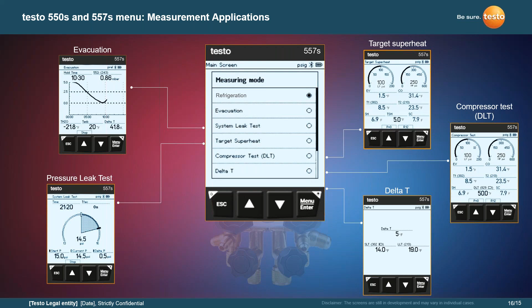If you use the wired pipe clamps, it measures T1 and T2 in that temperature area. When using the Bluetooth pipe clamps, like any other smart probe, there's a number on the back of each clamp. We don't signify high side or low side directly; instead, you take that number and assign it to the high side or low side when connecting it in the manifold. It's pretty easy to do.